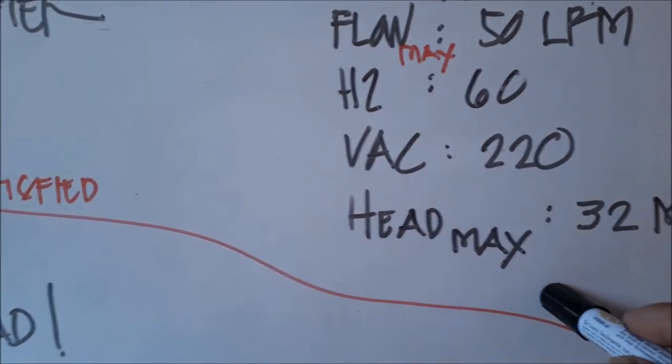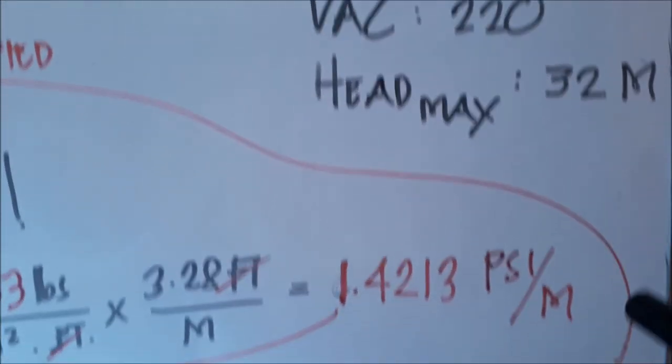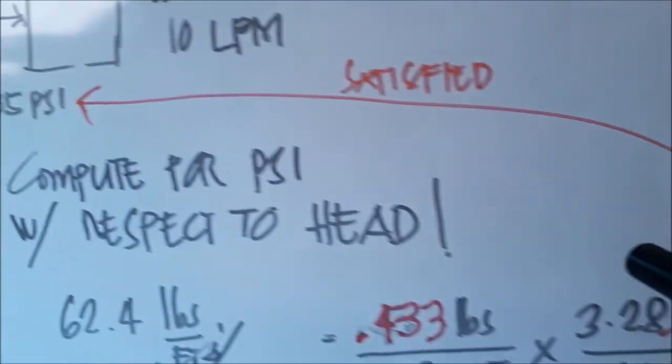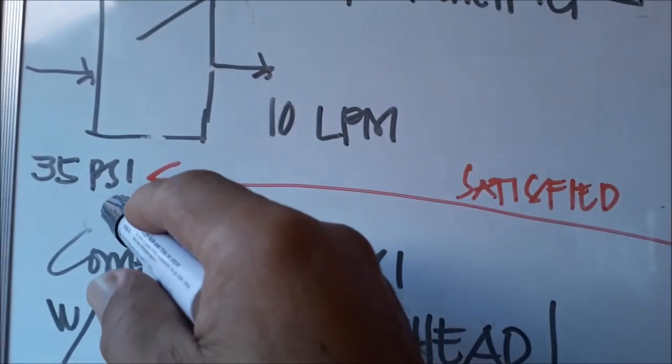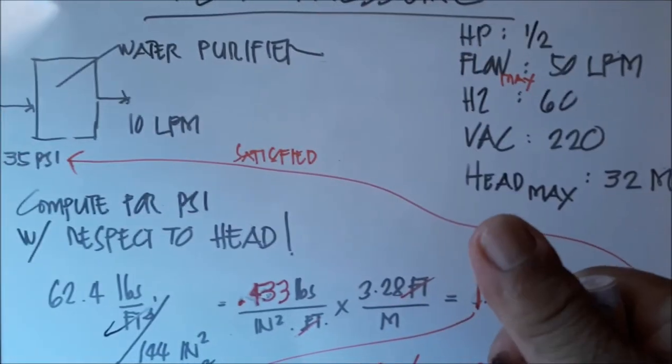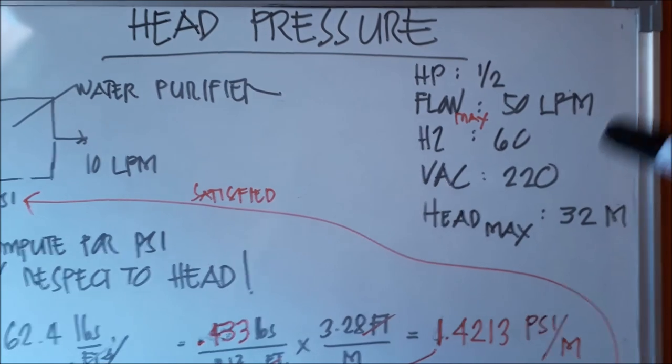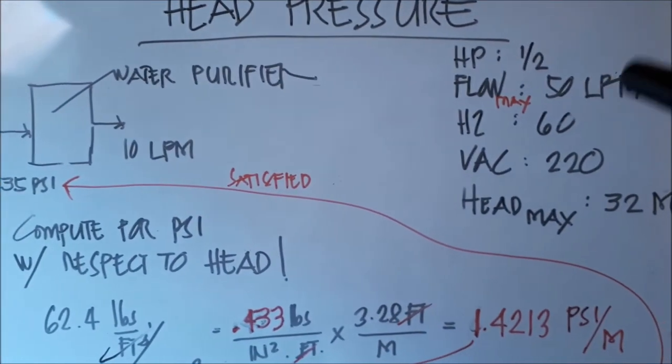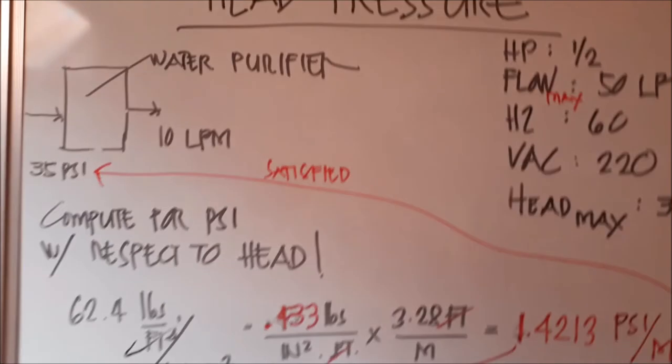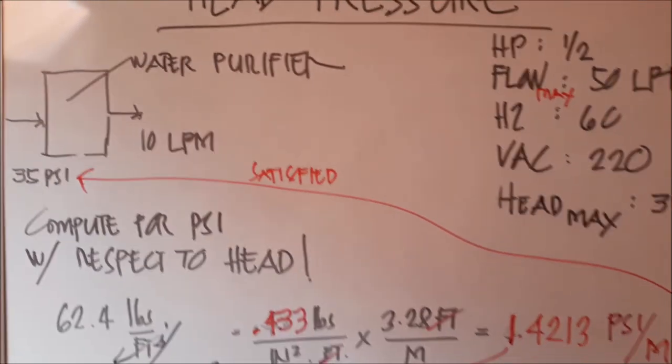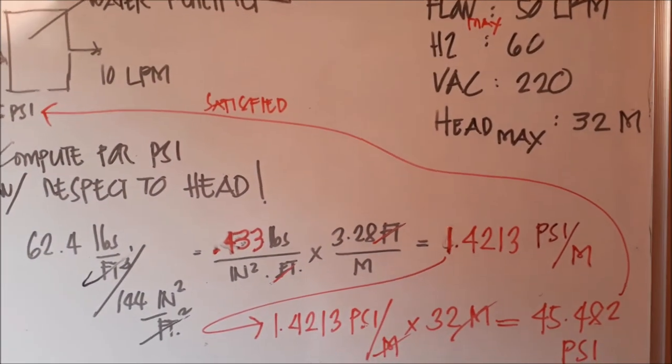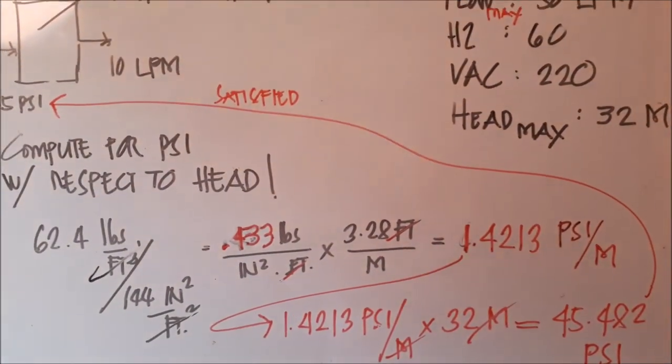Head is 32 meters, equivalent to 45 PSI. This is higher than the water filter inlet pressure requirement. Let's choose one-half horsepower instead of three-fourths. That's the conclusion of our topic from meter, converting it to PSI. Thank you very much.